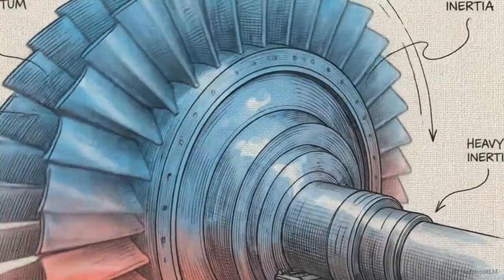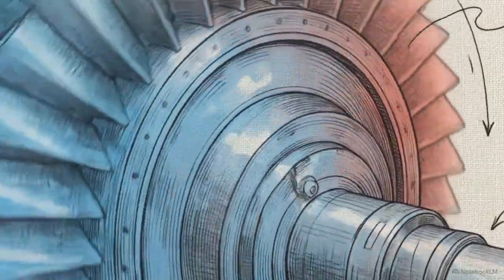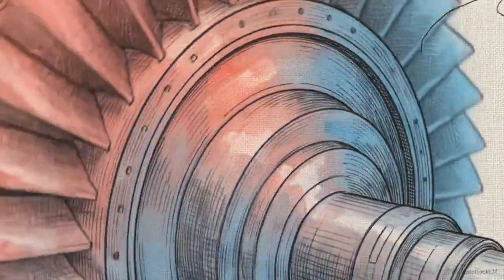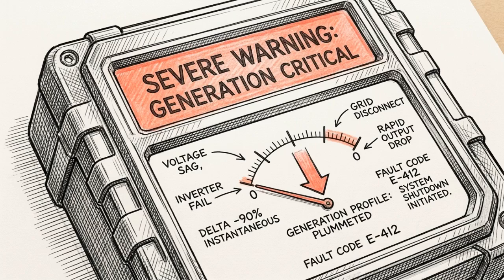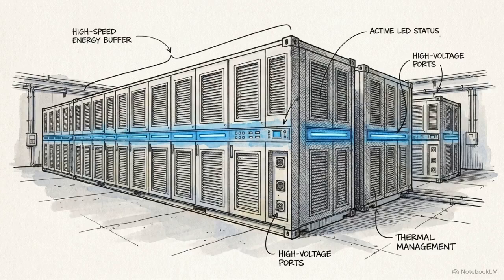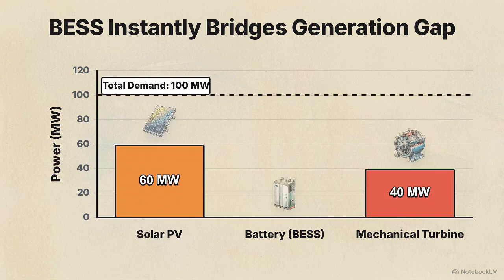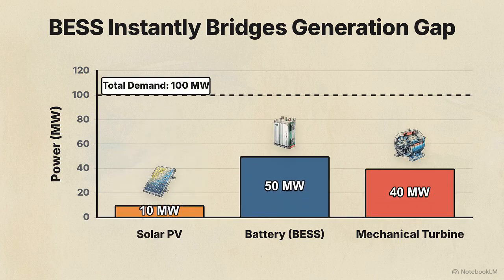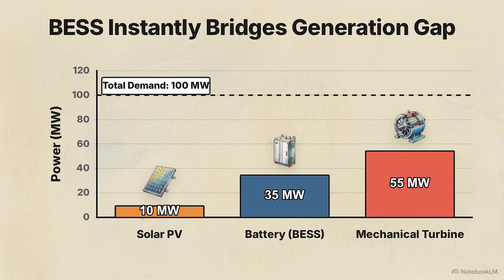But those mechanical assets have a physical limitation. They require time to spin up their heavy mechanical mass, meaning they cannot react fast enough to catch a sudden split-second drop in solar output. To bridge that immediate transient gap, the network relies on the Battery Energy Storage System, or BESS. This sequence shows the dynamic dispatch model in action.